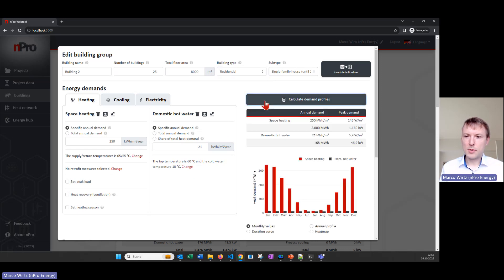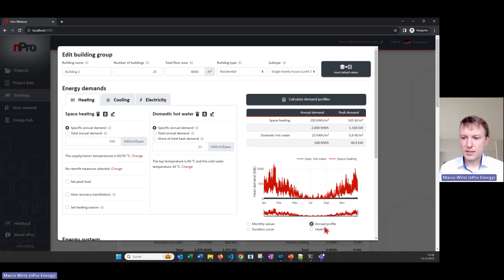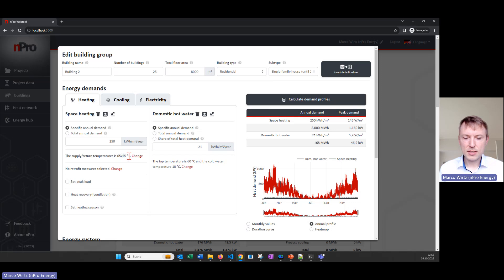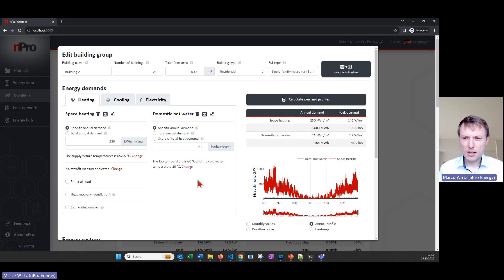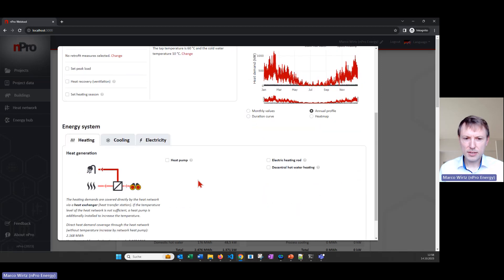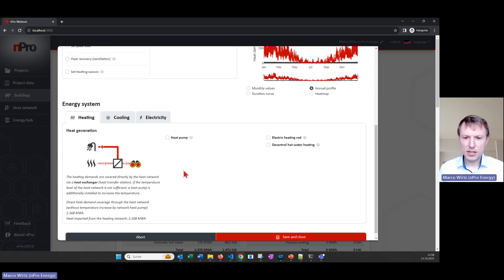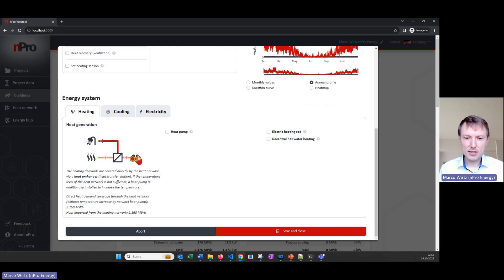We define the space heating demands and the domestic hot water demand. I click on 'Calculate Demand Profiles' and then we get the hourly profiles of the building. There's one important setting which is the supply and return temperature — here it's 65 degrees Celsius that is needed to cover the heating demands. This should always be smaller than the network temperature so that the network can really supply the building directly. At the bottom we have the energy system; in this case we don't need to change anything because we just have the heating network with a heat exchanger that then covers the domestic hot water demand and the space heating demand.